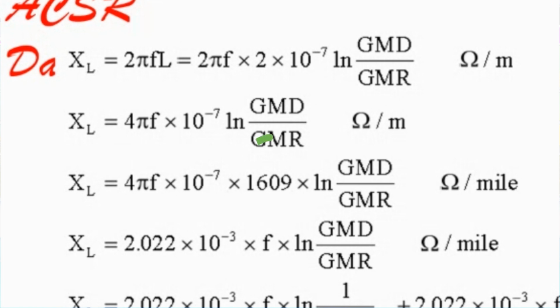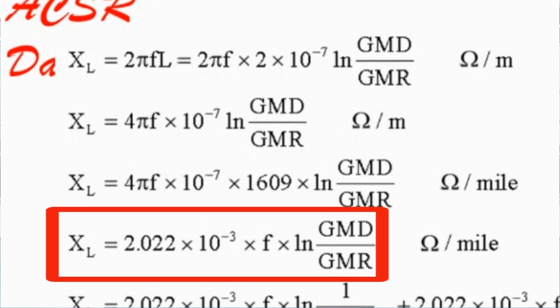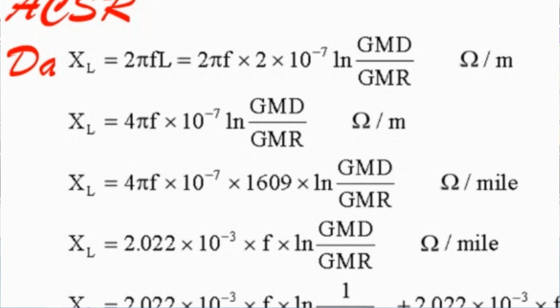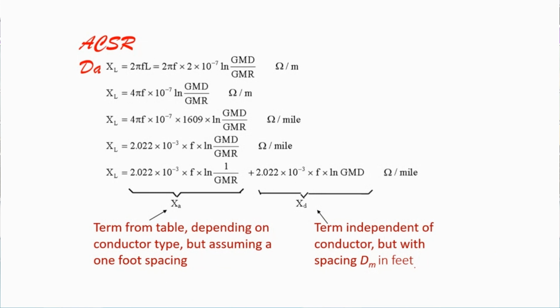I multiply by 1609 only to get it per mile. You know the relation between meter and mile - each mile is 1609 meters. It will be reduced to this. If you multiply this 2 by F, I'm keeping F because it depends on whether you're using 50 hertz or 60 hertz in some countries. If you do the simplification, you'll get 2.022 times 10 to the minus 3 multiplied by F ln GMD over GMR.